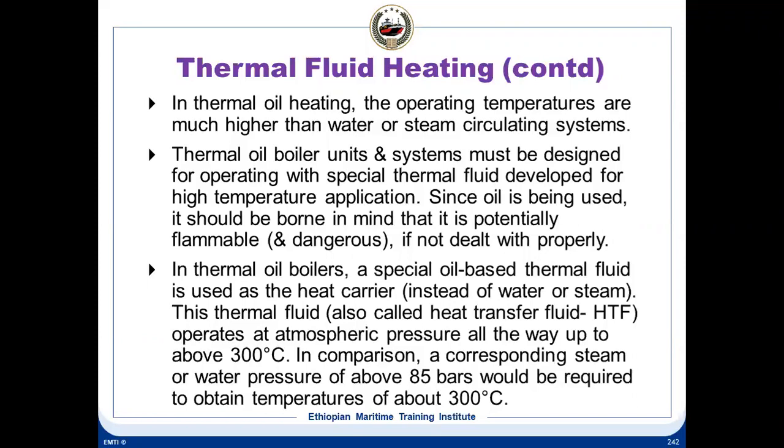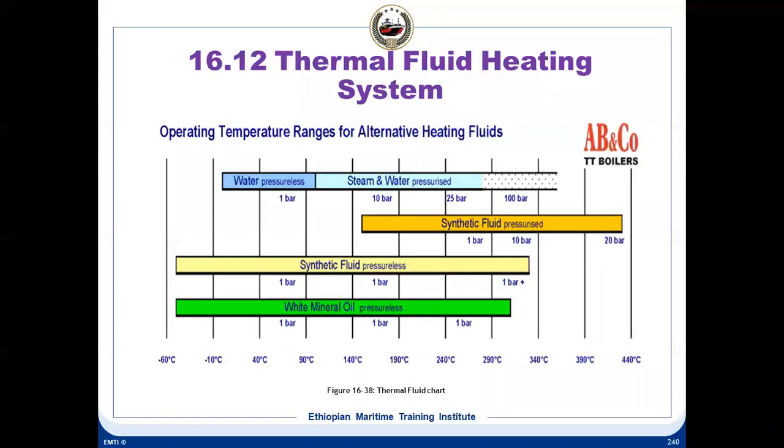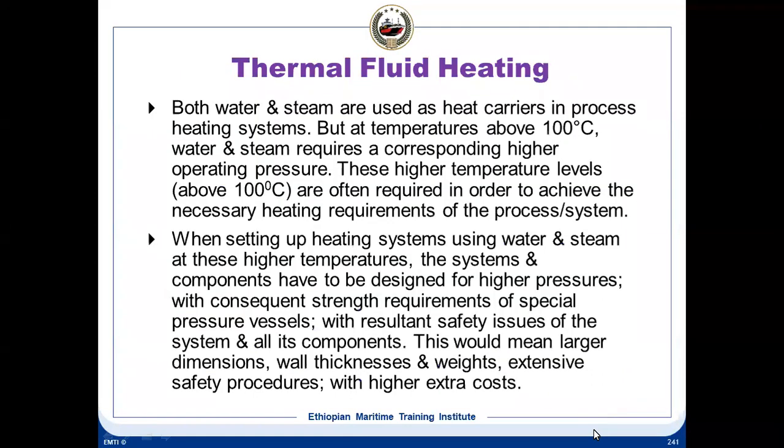Always thermal fluid is used as the heat carrier instead of water or steam, and this thermal fluid, also called heat transfer fluid, operates at atmospheric pressure all the way up to above 300 degrees centigrade. So you see a difference with steam. We have already seen that in the graph. It operates well above 300 degrees centigrade, white mineral oil, pressureless. At the same 300 degrees centigrade, you require steam or water to be at 100 bar. So these are the other advantages.